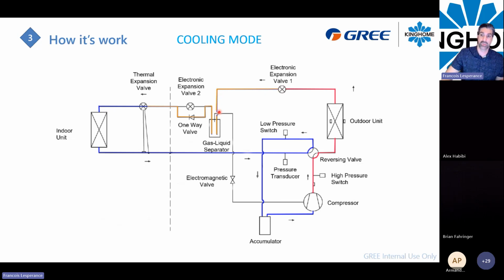Going out here, it will drop into a gas liquid separator. This cylinder here will be full of liquid refrigerant. On the other side, the system will pump out 100% liquid refrigerant, and we will hit a bypass right here. We have a secondary EEV, but in cooling mode this one is not in use. The refrigerant will flow by the easiest way, and it will hit this one-way valve and go out to the indoor unit. At this point, it can be your air handler, or it can be the A-coil.